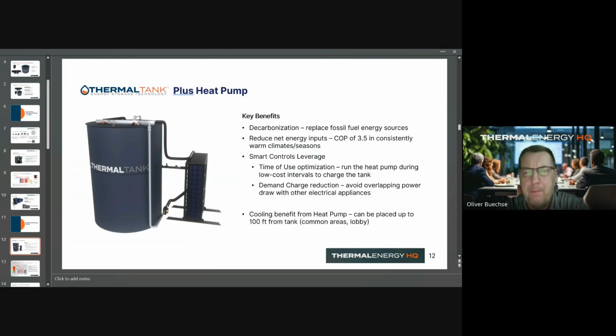Well, it's an ideal setup to maximize the capabilities of both technologies. On the heat pump side, think of those devices—they're like the little engine that could. You look at them and think there's no way that something putting out 26 kilowatts on the bigger unit, or down to a small-sized unit of 3.5 kilowatts, can build enough thermal potential to satisfy needs. That's where the idea of the storage tank comes in, because you can take that flexible storage platform we have and build in that capacity, so the heat pump, when it has the opportunity for demand charge reduction or time-of-use optimization to run, can give you that full thermal charge, so you can utilize it when energy is expensive and/or when the need applies from demands within your process.